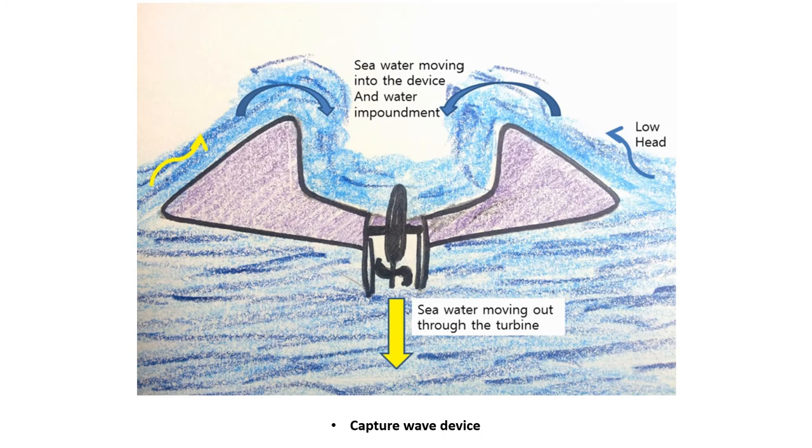The capture wave device is a floating device. As waves hit the structure, they flow up a ramp and over the top — hence the name overtopping — into a raised water impoundment reservoir on the device. Once captured, the potential energy of the trapped water is extracted using gravity as the water returns to the sea via a low-head Kaplan turbine generator located at the bottom of the wave capture device.